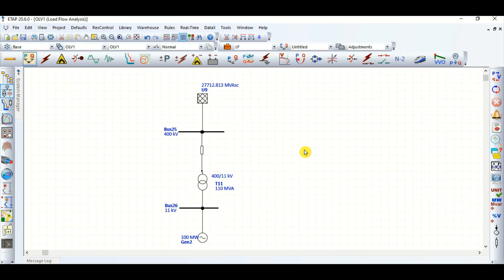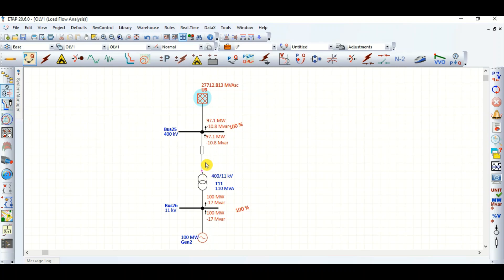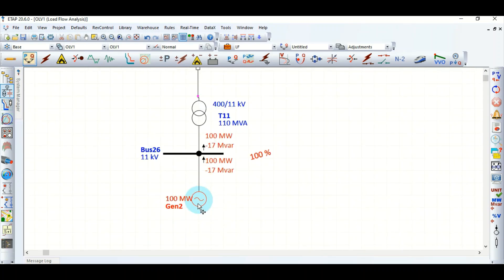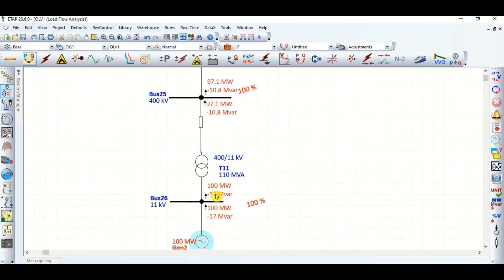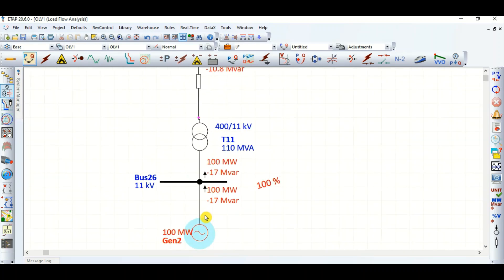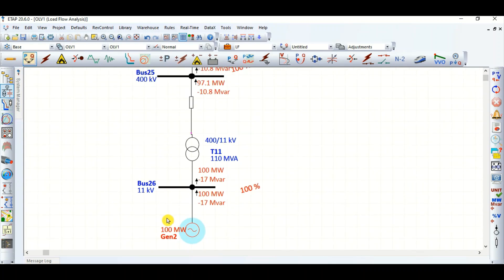In today's video I will discuss how to extract maximum reactive power from a generator in a grid-connected network. In this network you can see there is a 400 kV grid, transmission line, generator step-up transformer, and a 100 megawatt generator. The generator is absorbing 17 MVAR reactive power instead of supplying it towards the grid.